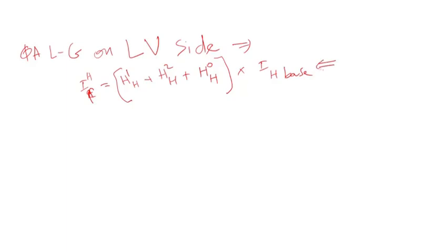So once you calculate this, this is phase A basically. It's no longer symmetrical component, zero sequence or negative sequence. This is the total current that will flow through phase A on the high side. In this case, as an example, I'm going with 345 kV. So if you multiply by the high voltage base current, then the high voltage winding has to handle that. It has to carry that current, so it has to be sized for this current, basically.